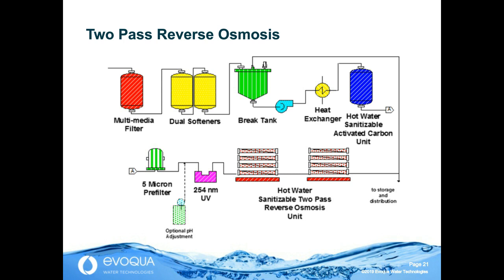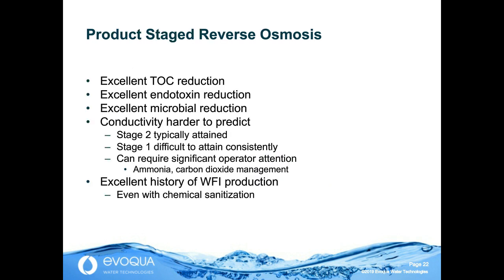And if we look at the history of these units, they're very good in attainment of TOC, endotoxin, and micro requirements for WFI. The conductivity is a little harder to predict. They're almost all going to attain at least stage 2 conductivity. They may attain stage 1 conductivity, but holding that steadily without operator intervention can be difficult due to management of ammonia and carbon dioxide. But they can produce WFI, a configuration like this, and even in the days of chemical sanitization, no hot water, the history was still pretty effective.